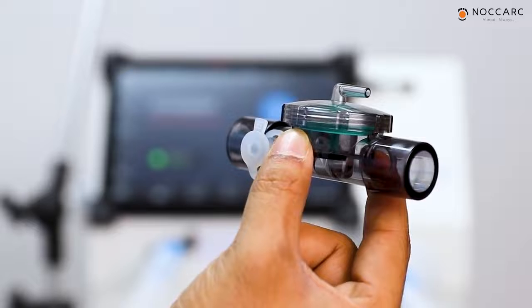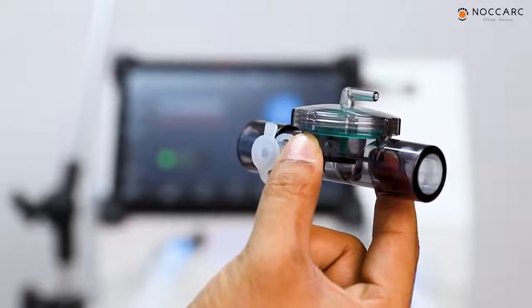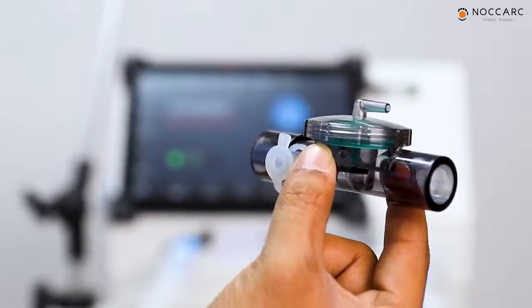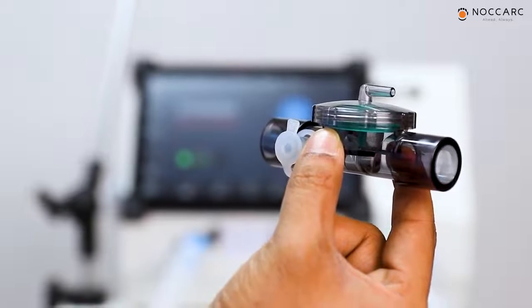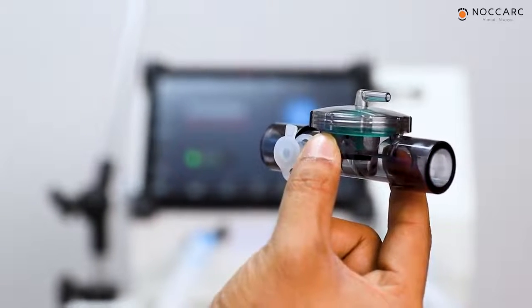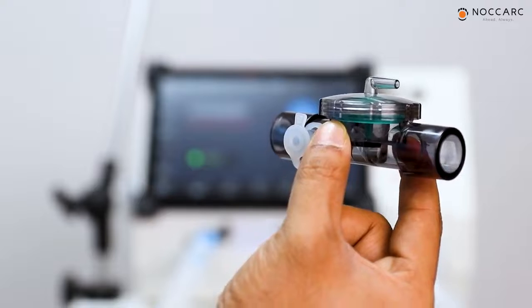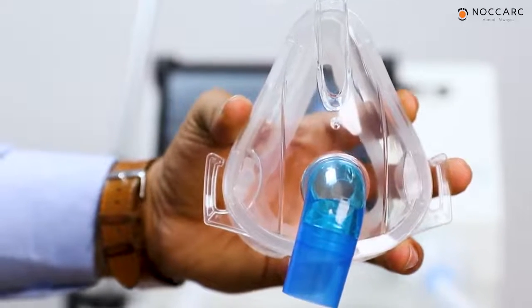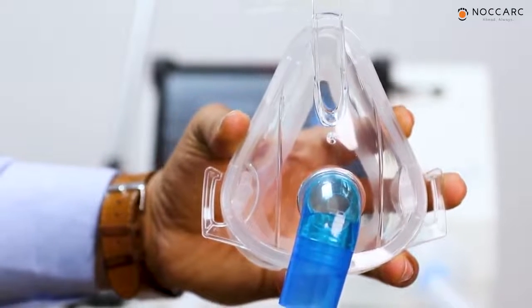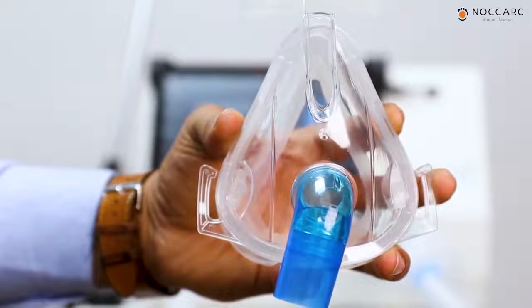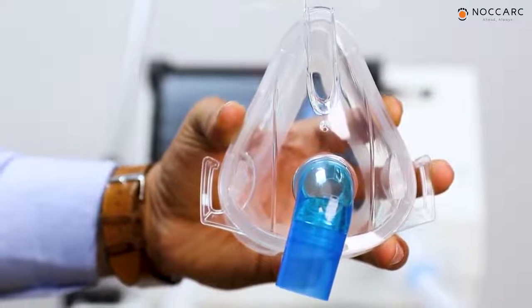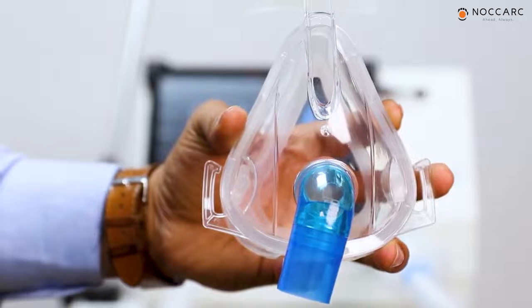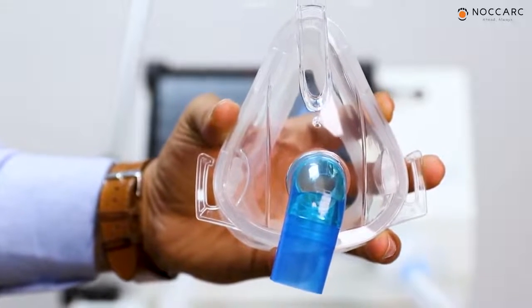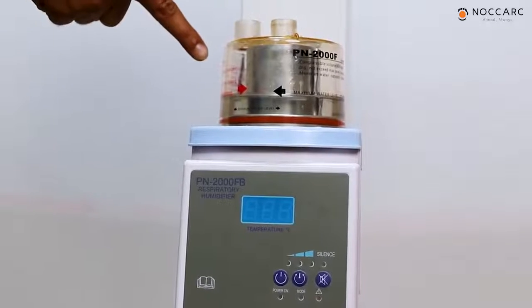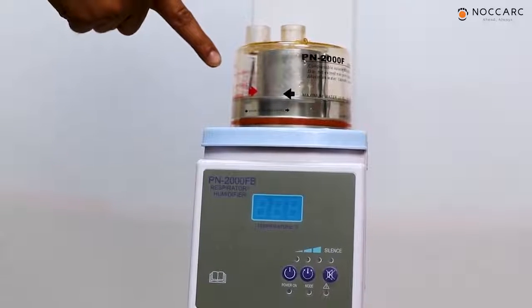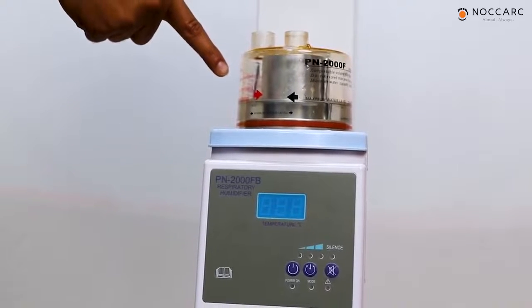Always autoclave the reusable active exhalation valve. User can use active exhalation valve up to 10 times after doing autoclave. Always use non-vented mask for non-invasive ventilation. It will help to keep leakage as low as possible and proper ventilation. Always use sterile water in humidifier chamber for proper humidification.